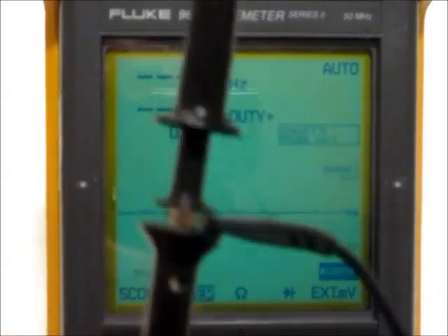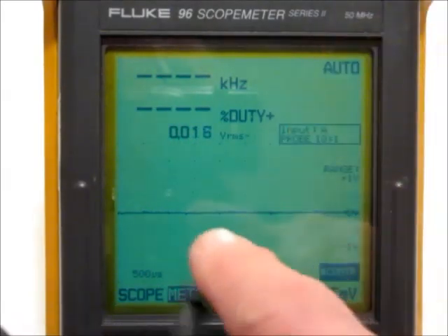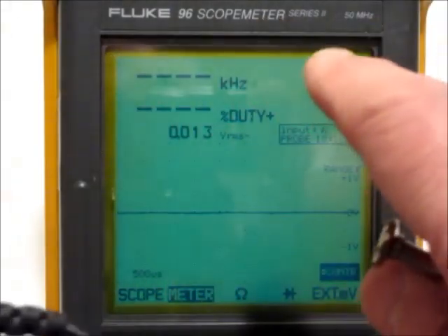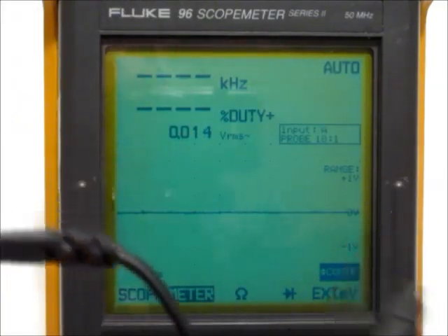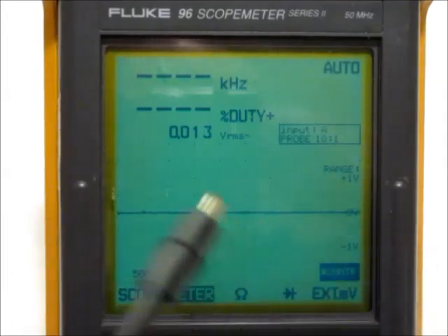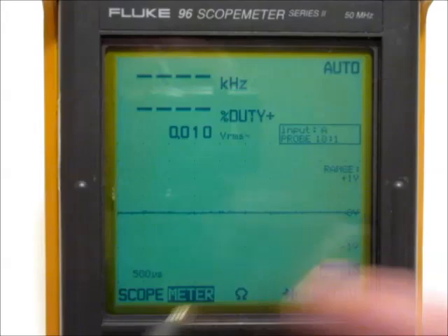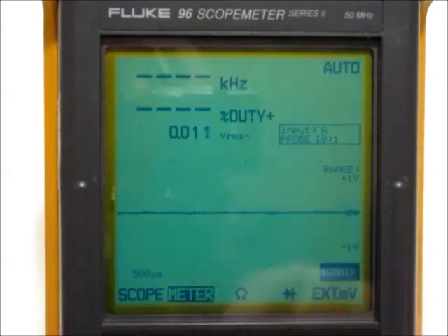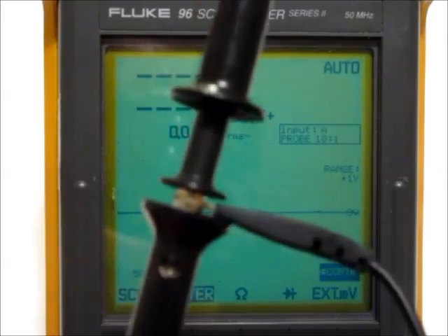Right here I'm showing a scope probe which I have on hand, and I wanted to put it on this old Fluke 96 scope meter. Now, while the Fluke scope meter has its own internal mechanism where you can set it up so it will adjust itself to a Fluke probe, you can also put any probe on the Fluke scope meter, a typical 10-to-1 probe. And here I've got it, there's 1 times and there's 10 times.